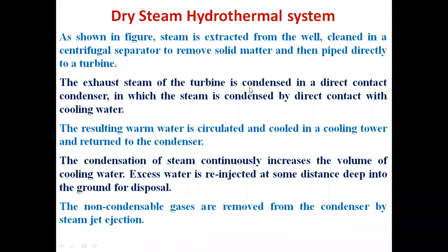The exhaust steam of the turbine is condensed in a direct contact condenser, in which the steam is condensed by direct contact with cooling water. The resulting warm water is circulated and cooled in a cooling tower and returned to the condenser. The condensation of steam continuously increases the volume of cooling water in the condenser. Excess water is re-injected at some distance deep into the ground. The non-condensable gases are removed from the condenser by steam jet ejection.